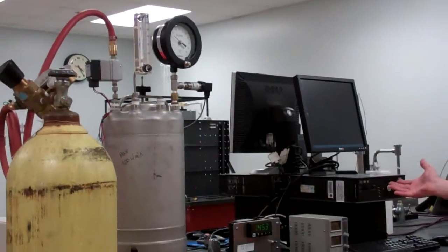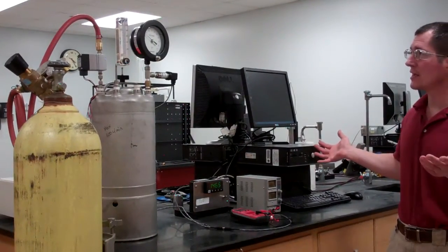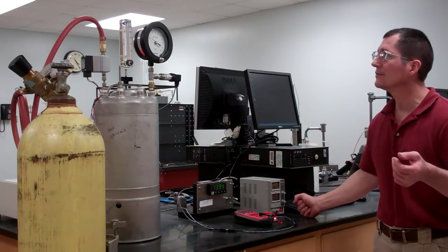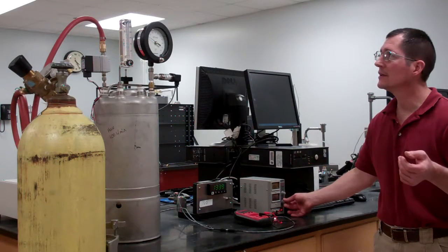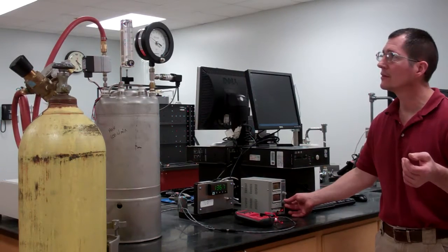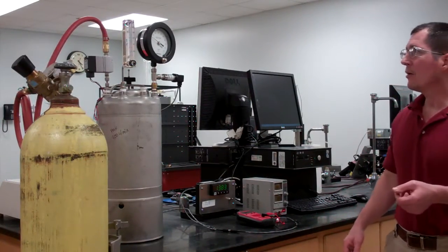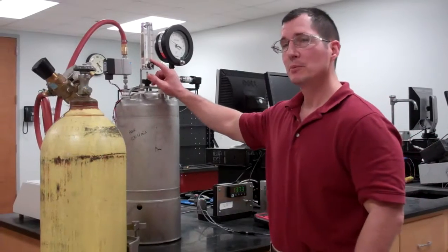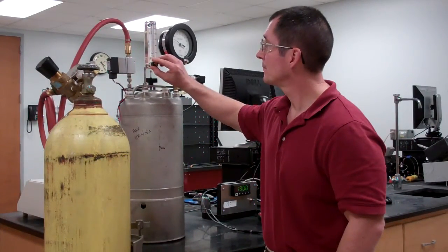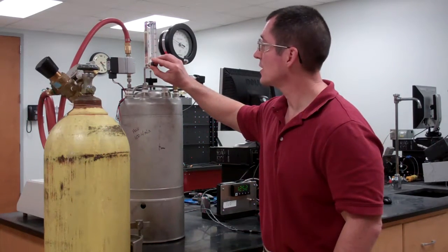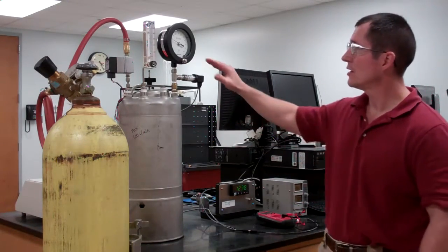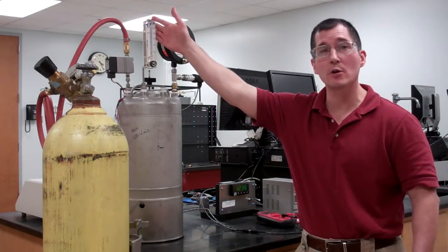And as you can see, when we stop changing the signal, the pressure stabilizes. And we're a little bit above, so we'll just reduce the pressure a little bit. There we go. And with a little bit of finagling, you can get it right at 15. Now, what happens though if you have some bleed off from here that reduces the pressure? So, as you would expect, with the same input signal, I haven't changed the input signal, our pressure has dropped because we've got some flow going out of our tank.